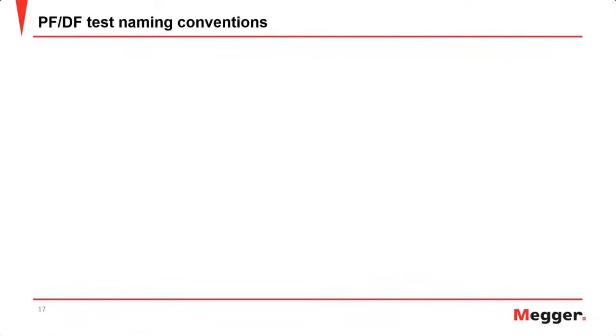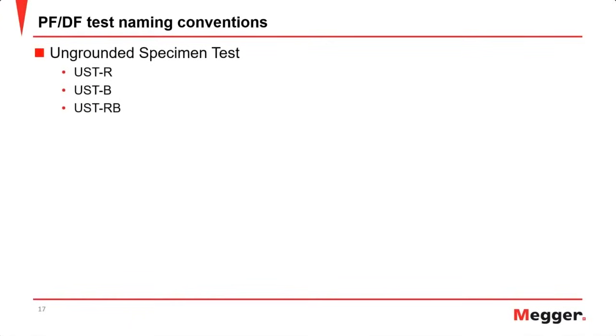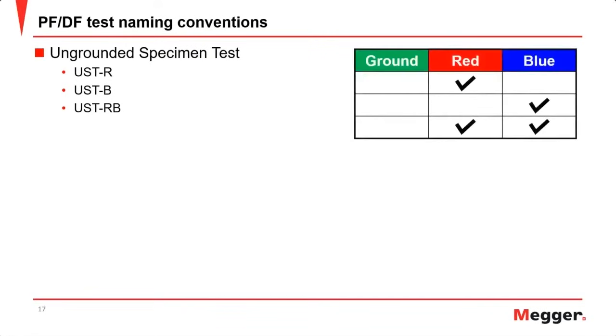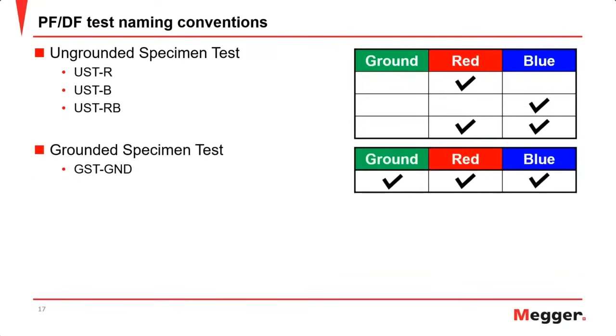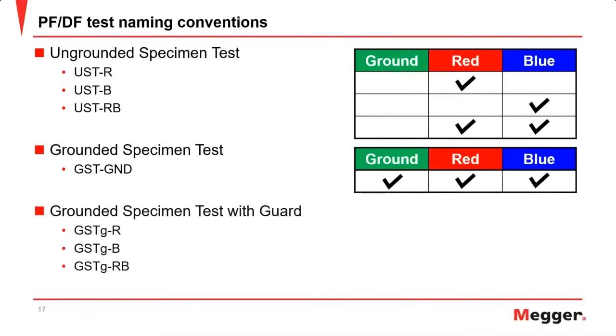So if we take another look at this, if we look at the ungrounded specimen test, we have UST-R, again standing for ungrounded specimen test, UST-R, UST-B, and UST-RB. And this means that, with your high voltage lead connected to your asset, you are going to measure the leakage current coming back on the red lead, the blue lead, or both the red and the blue lead. Next, we have the grounded specimen test, the GST-GND. We will be measuring the leakage current that comes back on all three channels: the ground, the red, and the blue. And then finally, the last one is the grounded specimen test with guard. You see that as GST-G and then -R, -B, or -RB.